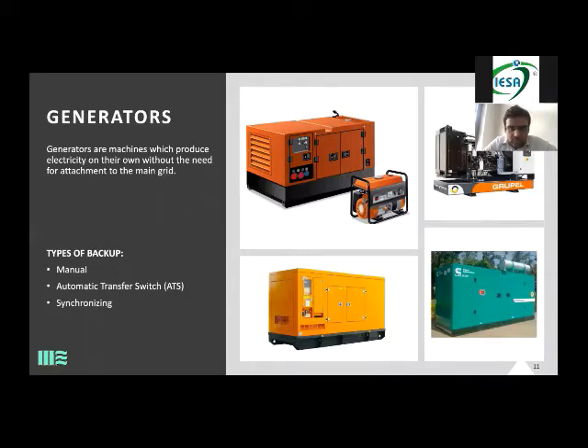If something happens on site, there is no delay; it is seamless power. In automatic, there is a delay of about a second, a flicker which happens. In synchronization, there is no flicker. So 80, 80, 80, they are running, the total load is 240. They are running on 80 kilowatts, 80 kilowatts and 80. If something happens to this genset, automatically its 80 will be divided among these two.